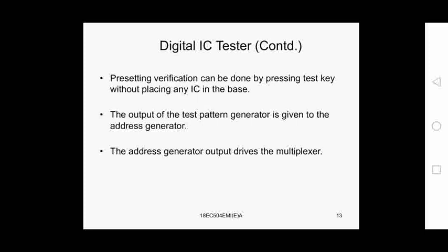So before testing, presetting verification can be done. Before testing any IC, we can have presetting verification by pressing the test key without placing the IC in the thumb wheel switches base. That is, without placing any IC in the base.